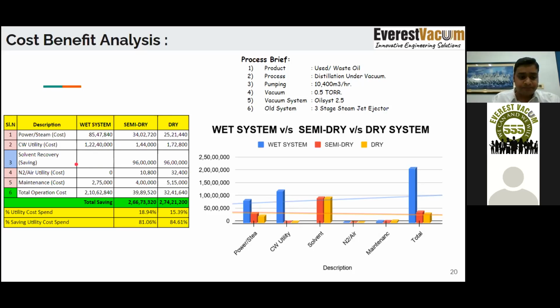Solvent recovery. There is no solvent recovery in the ejector systems, the wet vacuum systems, because the gases and fluid traveling inside these systems carry the vapors with them. So it is very difficult to re-distill the products out of that particular condensate. They do not have any nitrogen or air utility requirement. The maintenance cost is quite high, but reasonable as compared to the mechanical systems.